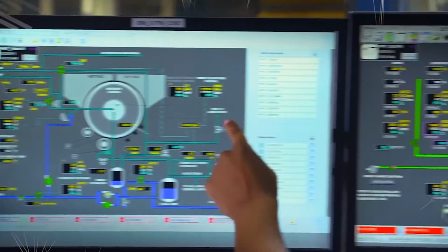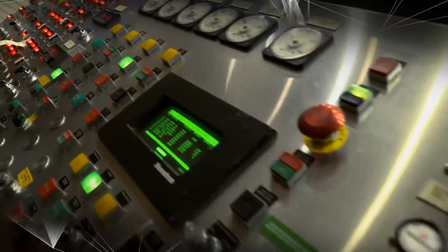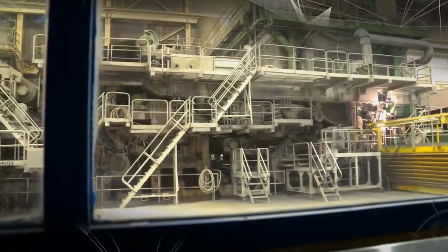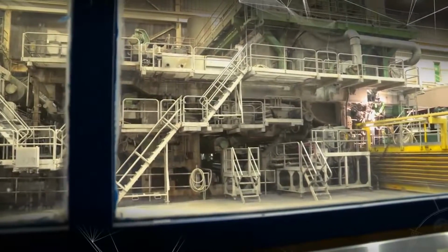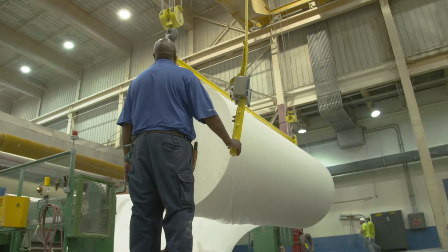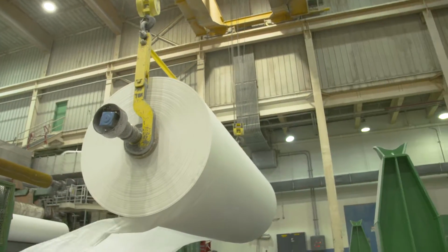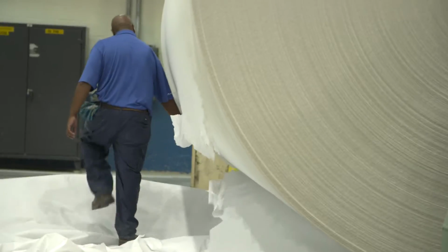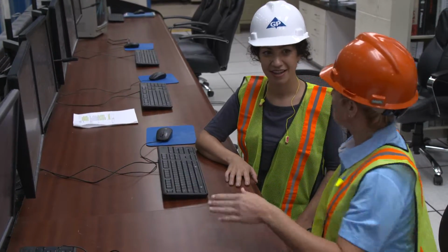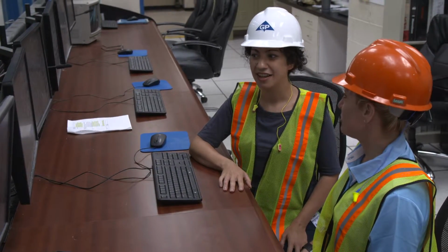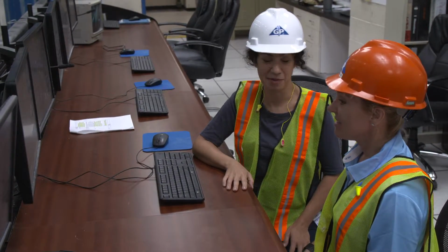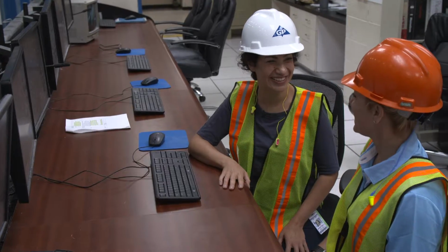With this third step of engineering, we're putting our design to the test, and it worked. The heat exchanger is now able to maintain a constant temperature, ensuring paper machine 16 is back to its productive self. So that's going to help keep the production line moving? Absolutely, it'll keep the paper coming off the Yankee very quickly. The operators will be checking this every shift, so we'll know it's functioning properly. So you just keep following this and we keep making paper? Absolutely. Well, thank you. Thank you.